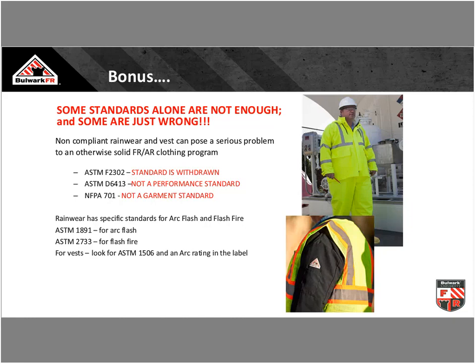Think about outer layers. Think about your rain gear. Think about your high-vis vests. A lot of utilities today and a lot of our electrical guys are being required to have high-vis safety apparel, and then when we put them out in the rain, they're required to wear rain gear. Guess what? That rain gear is now the outermost layer. That rain gear has to be tested to the hazard. In this case, it has to be ASTM 1891 for arc flash, ASTM 2733 for flash fire.